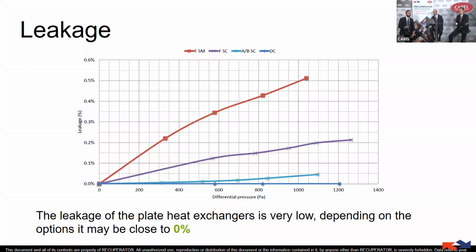That means we can have a leakage lower than 0.5% of nominal airflow. In the graph we can see different heat exchangers with different types of sealing that can reach almost 0% leakage rate. That is a really low value. In this case we don't have to care so much about differential pressure, because the leakage is always so low that we never have cross-contamination.